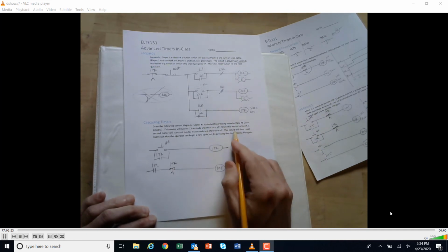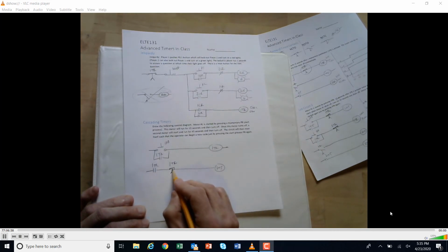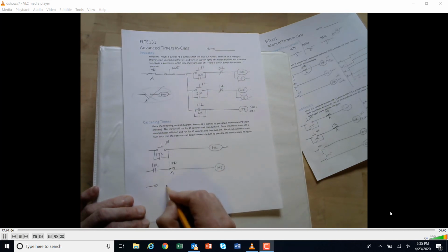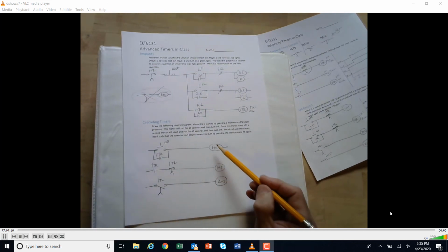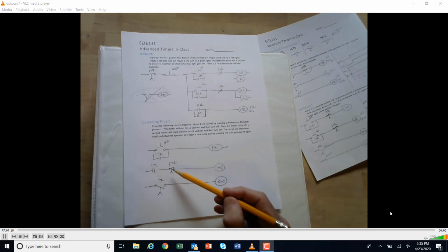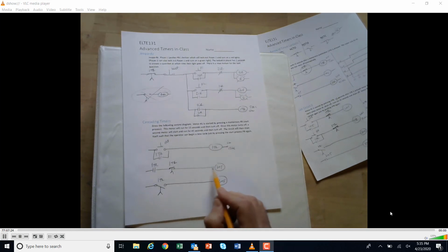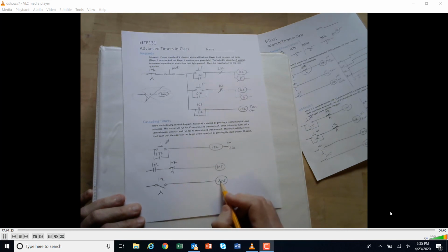Okay. Once this motor turns off, a second motor will start. So what we need is this time relay turns off one motor, but it turns on another motor. So this one is open and it's time closed. Okay. Once again, this timer, after it times out, it's an on delay, 15 seconds. This one opens, this one closes. This one goes off, this one goes on. And then it says that this one runs for 45 seconds and turns off.